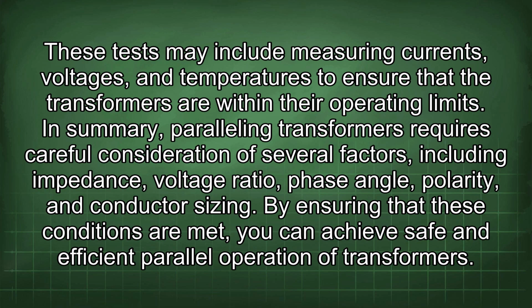In summary, paralleling transformers requires careful consideration of several factors, including impedance, voltage ratio, phase angle, polarity, and conductor sizing. By ensuring that these conditions are met, you can achieve safe and efficient parallel operation of transformers.